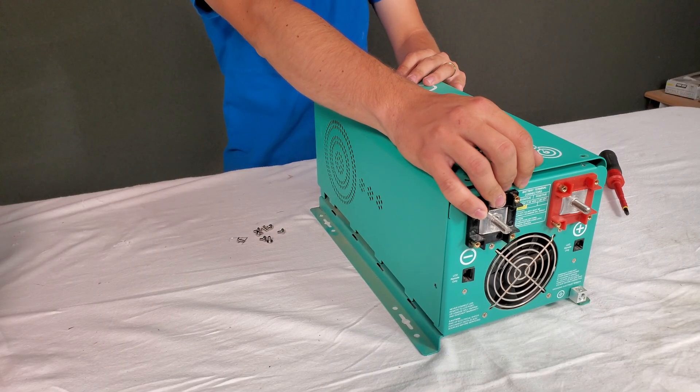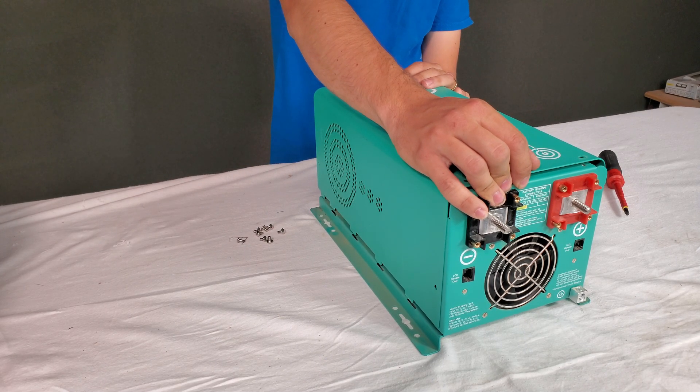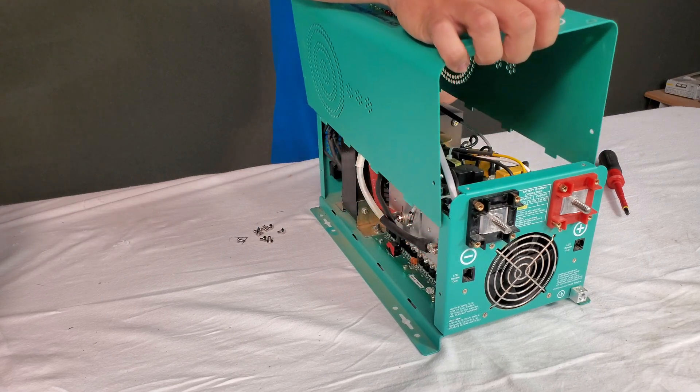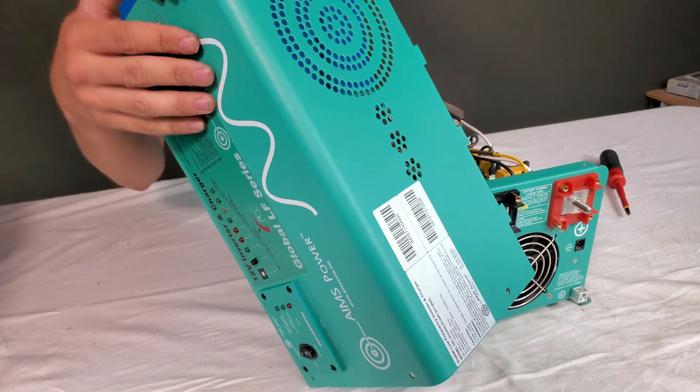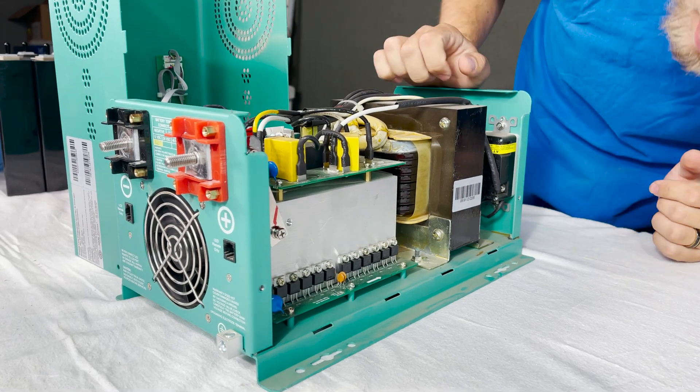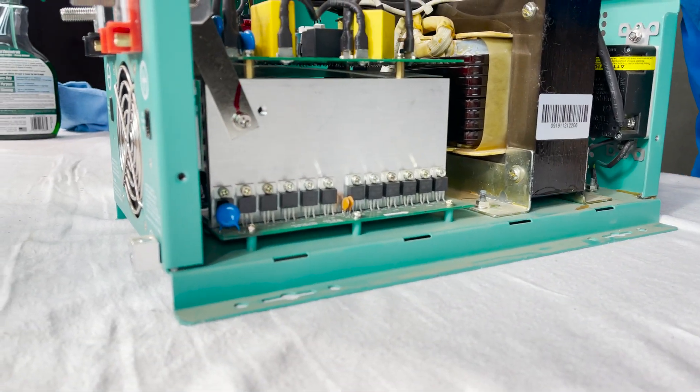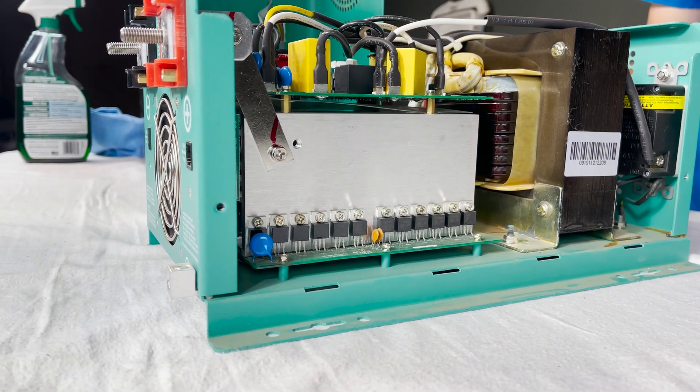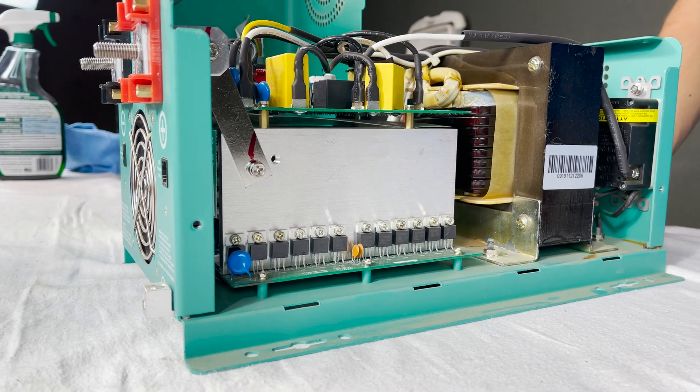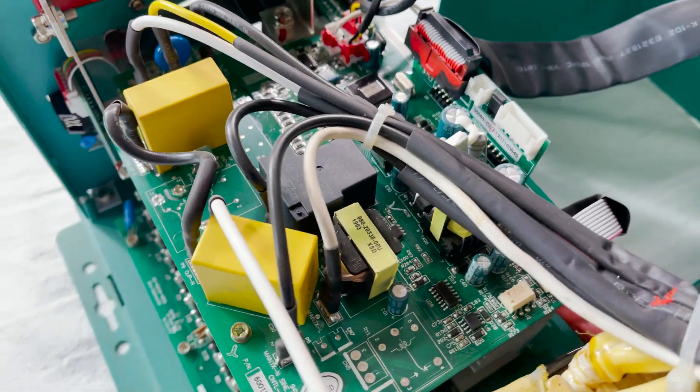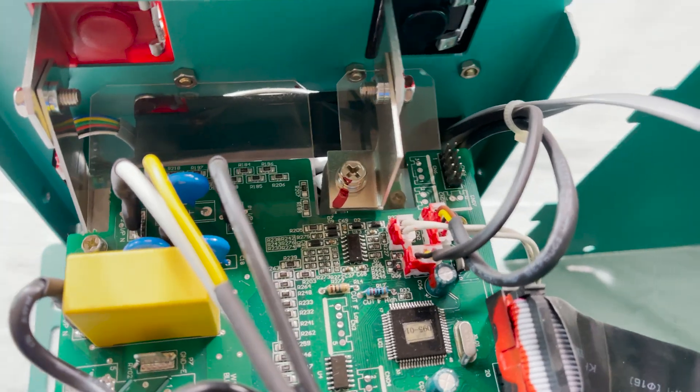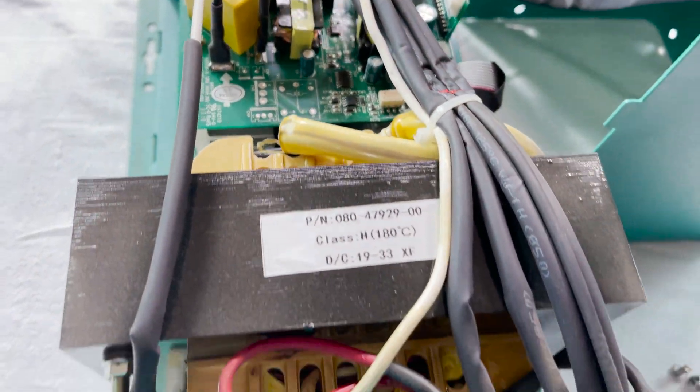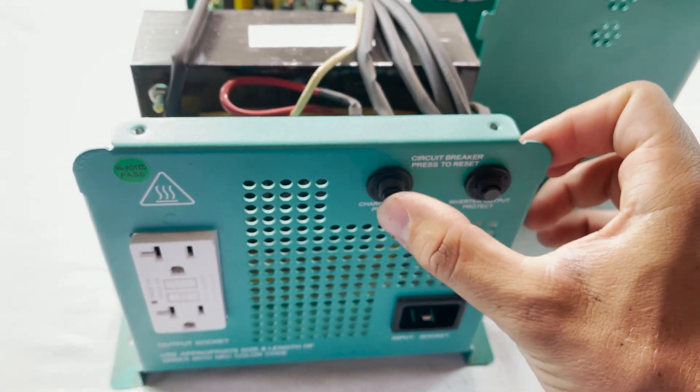But before I do this let's talk about what I think is going to be in here. I think there's going to be blown FETs and probably a stuck transfer switch because that's how I've had these go before. Let's see. Everything appears to be okay, I don't see anything too crazy. I mean I checked the breakers, they're perfectly fine.